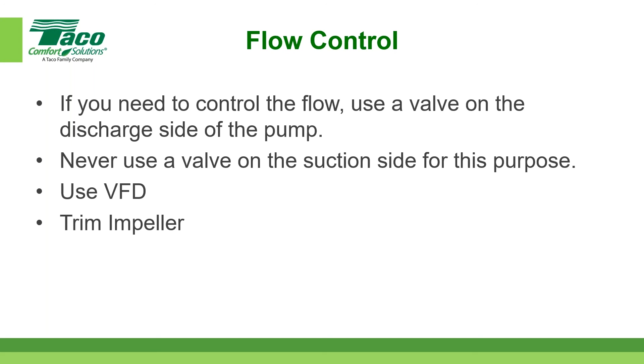But you can also trim impellers, right? So that's something to consider if you get into a bind. For whatever reason, you have to look at that impeller size and start thinking about whether you want to trim it or not, based on horsepower. We're not talking about curves here, we've done that in other presentations. If it's the right horsepower, you can increase the impeller size to get some more oomph without adjusting too much else on the project. So there are different ways you can control flow, but I think nowadays VFDs are the way to go.